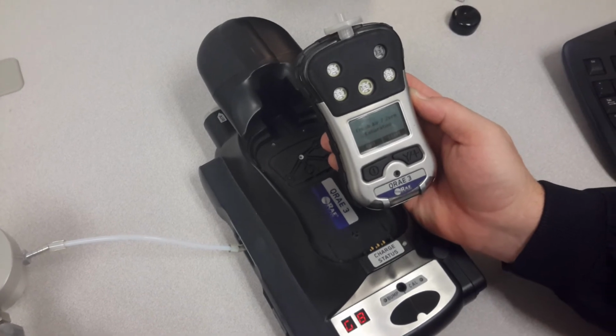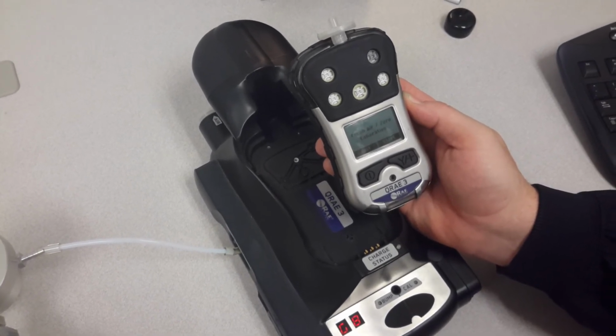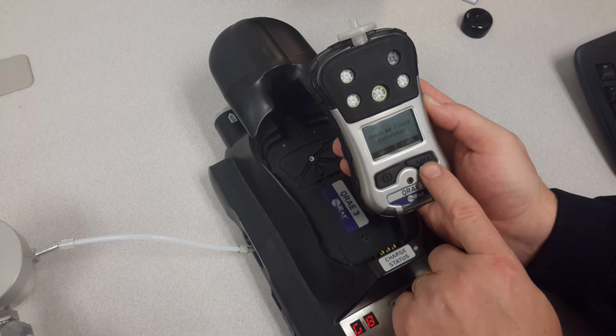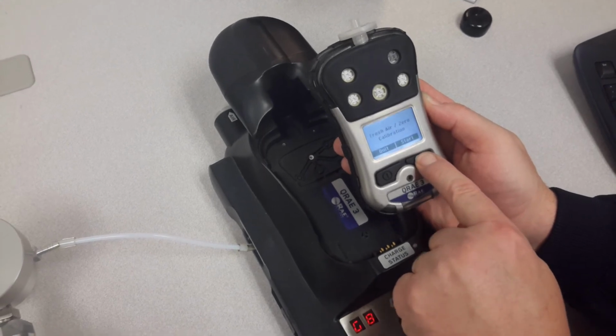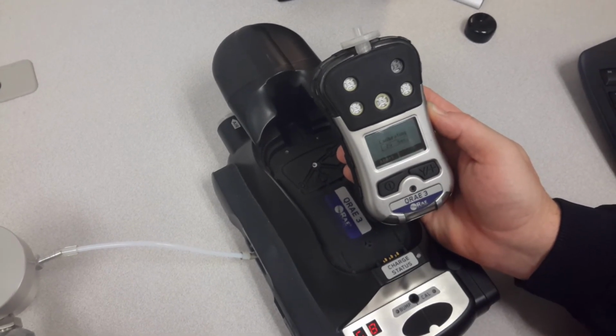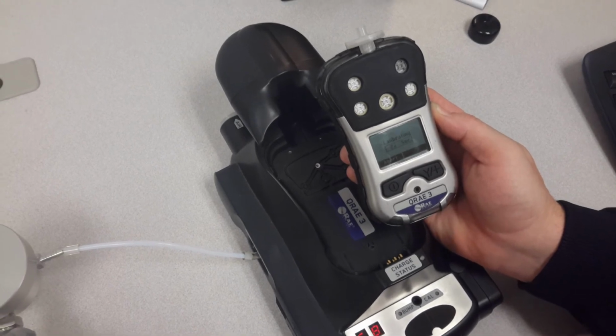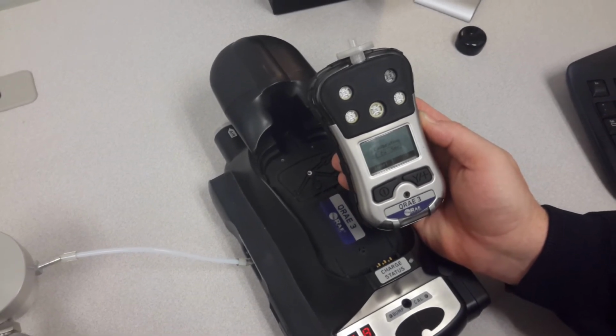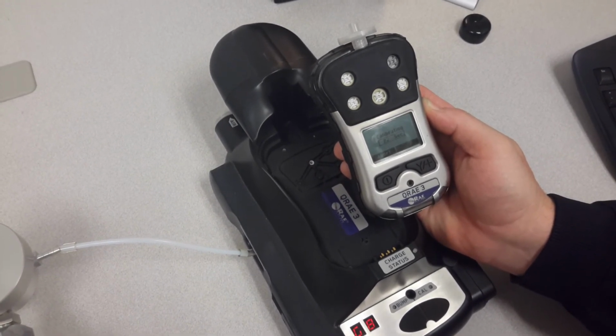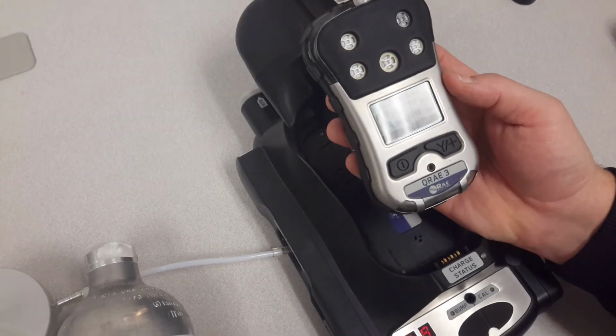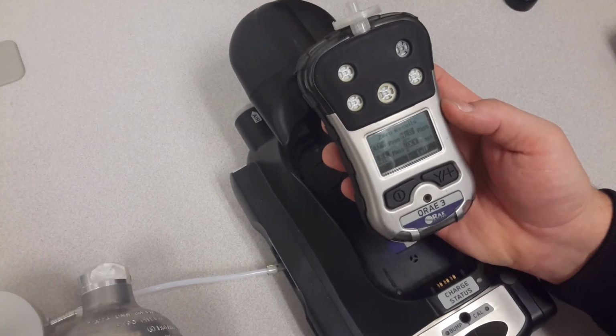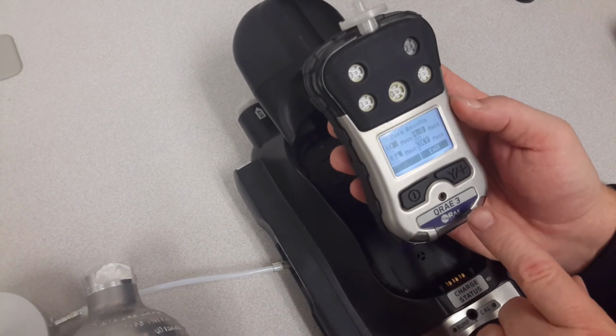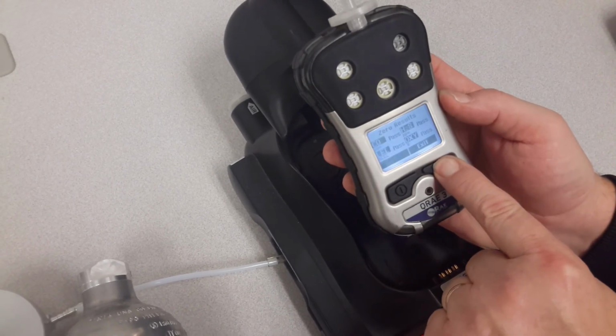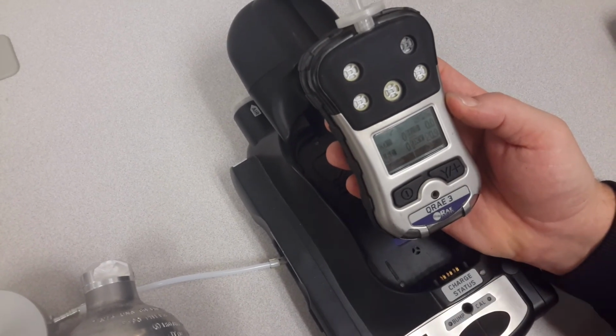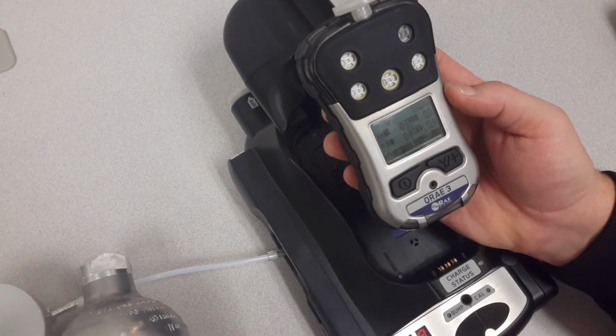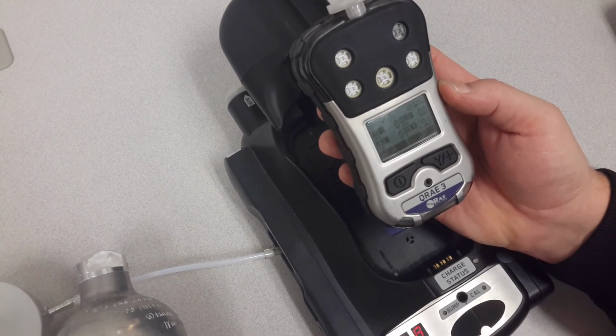So it does say here now that to do a fresh air 0 calibration, you go ahead and hit start, and it'll be about 30 seconds, and it should be complete. And after this, the machine should turn to normal mode. Okay, so the unit finished out its 0 calibration. It's going to the results screen here. You press the exit button, and now the machine's back into normal operation mode.